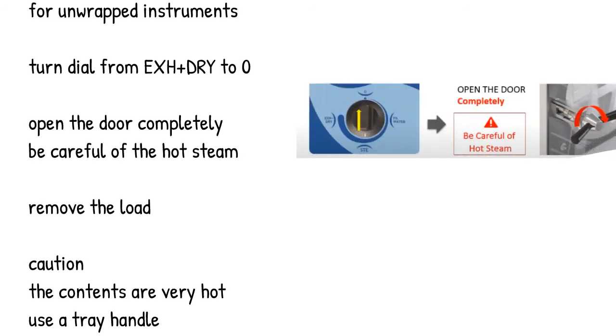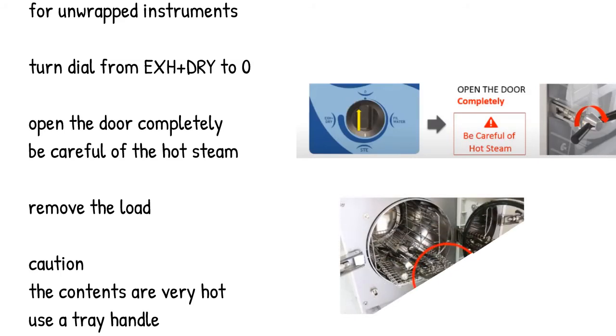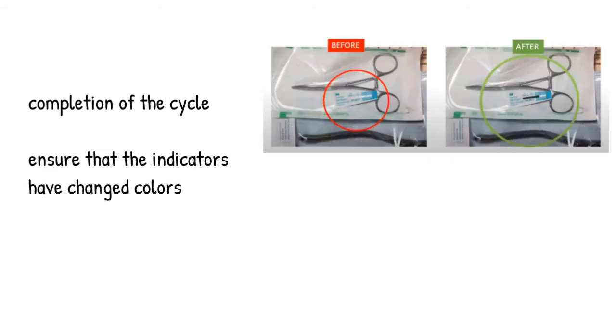For unwrapped instruments, turn the dial from EXH plus dry to 0. Open the door completely. Be careful of the hot steam. Remove the load. Caution: the contents are very hot. Use a tray handle. Completion of the cycle. Ensure that the indicators have changed colors.